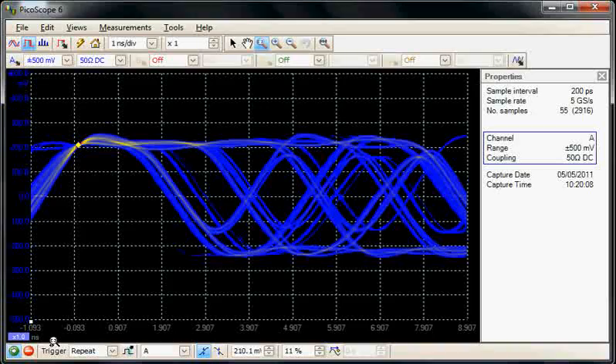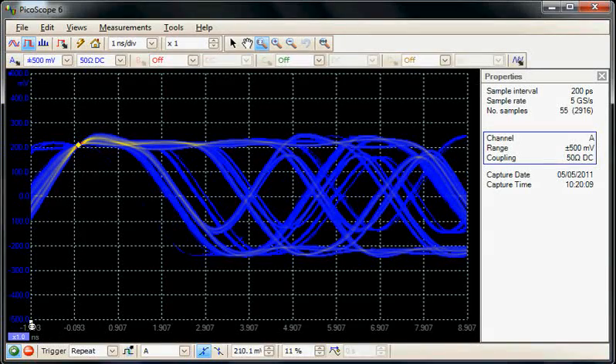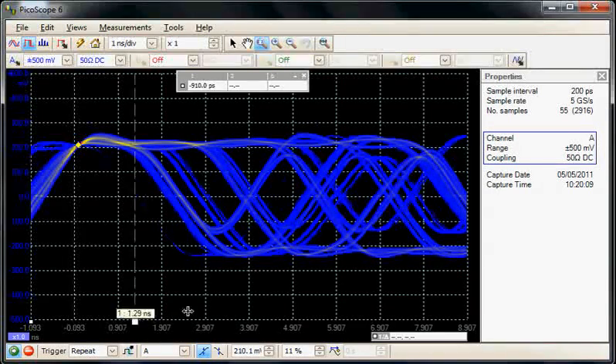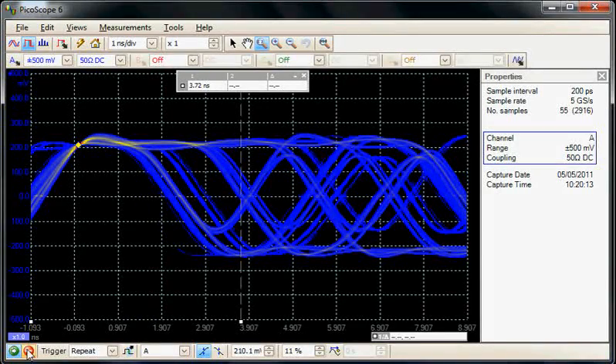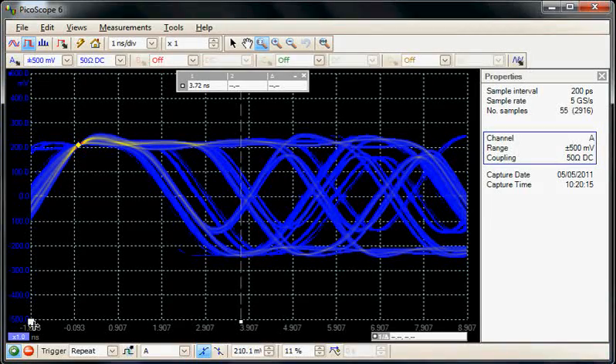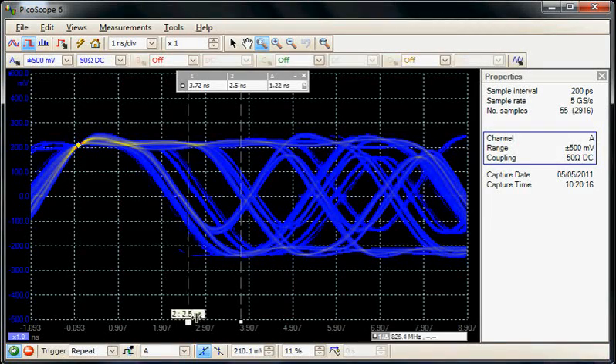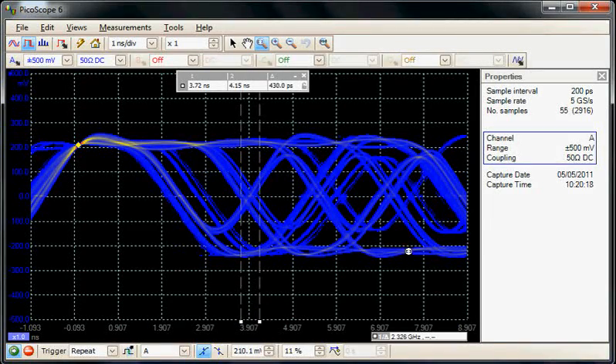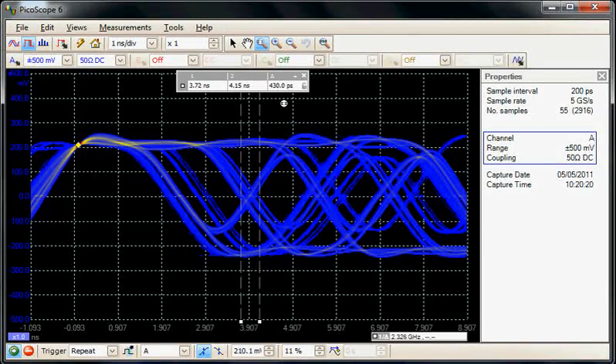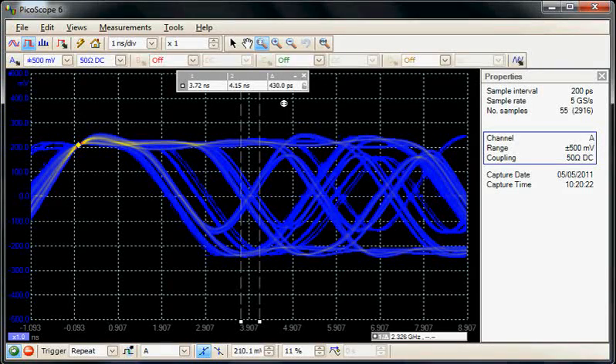So again we could use the cursors to now measure the data jitter on this particular signal. So here we see we're getting something like 430 picoseconds of jitter.